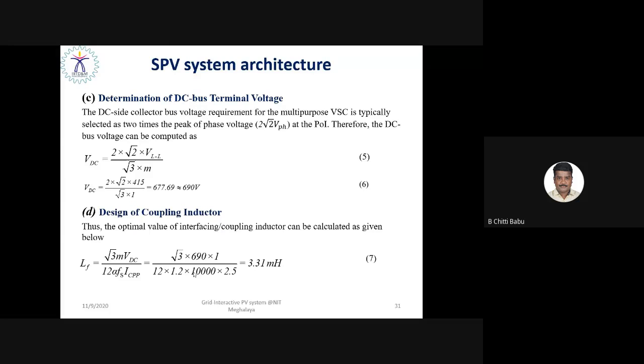So the DC component is injected into the grid through the interfacing transformer, and ultimately the transformer core is going to be saturated due to double frequency oscillation or due to the DC offset. So sometimes the DC offset component may saturate your core, and hence there is an inherent generation of second order as well as third order harmonics. So overall system performance is going to be degraded, and moreover the efficiency also decreases. The interface coupling inductor is used to reduce the DC current ripple on the inverter output stage, and it has been designed at 3.31 millihenry, assuming that the switching frequency of the inverter is about 10 kilohertz.